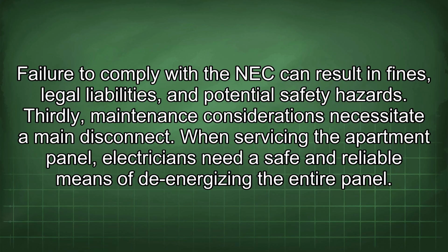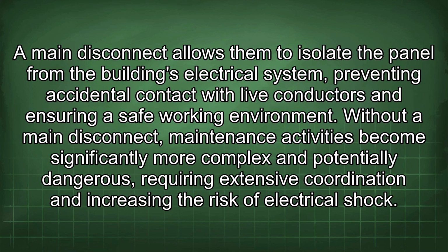Thirdly, maintenance considerations necessitate a main disconnect. When servicing the apartment panel, electricians need a safe and reliable means of de-energizing the entire panel. A main disconnect allows them to isolate the panel from the building's electrical system, preventing accidental contact with live conductors and ensuring a safe working environment.